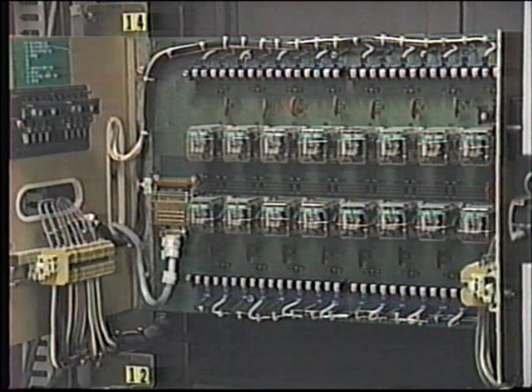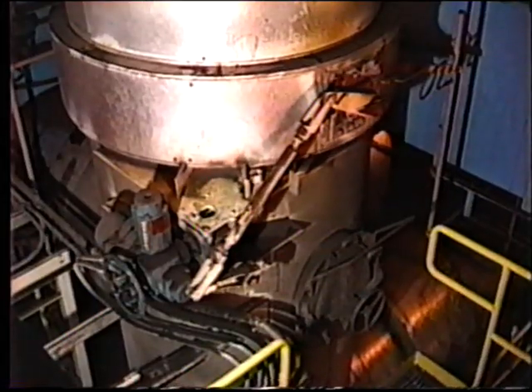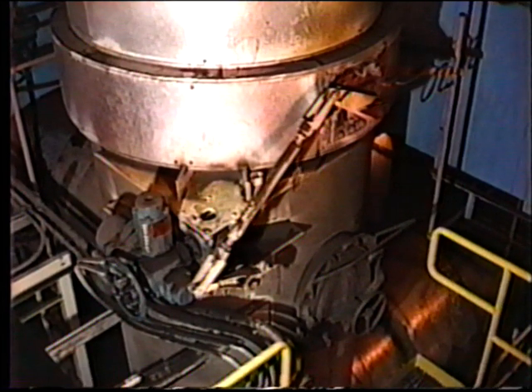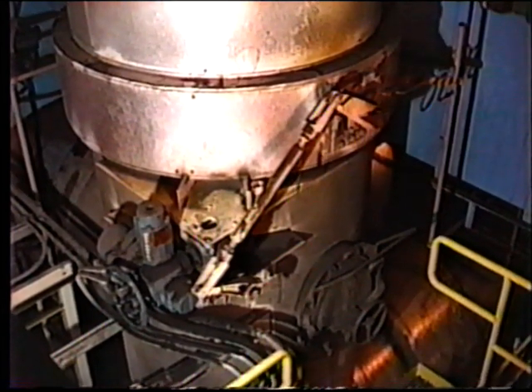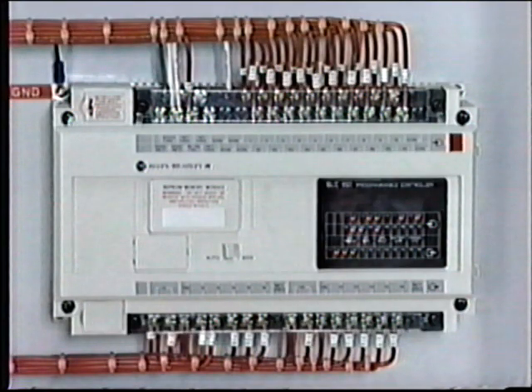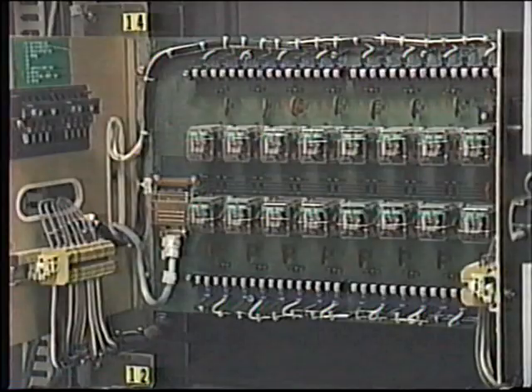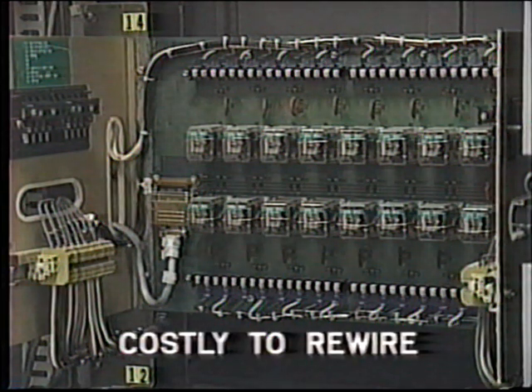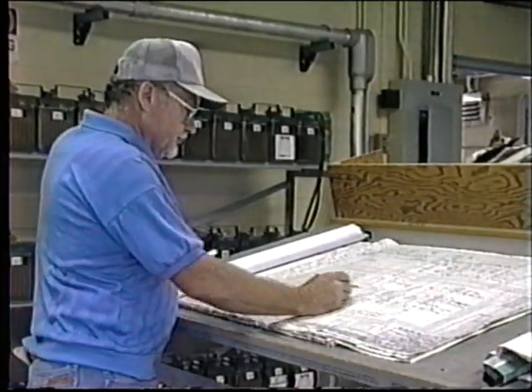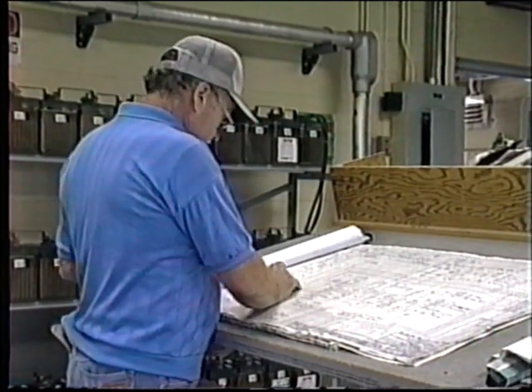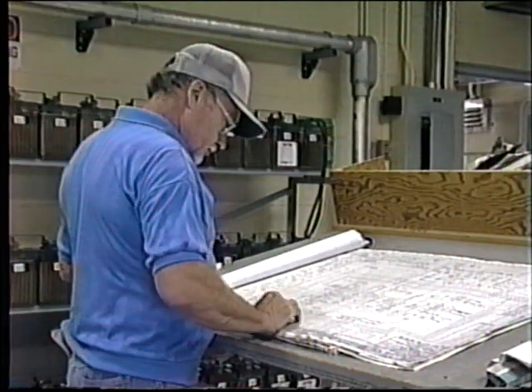Traditionally, control has been performed by hardwired relays which open or close contacts to operate control devices in a specific sequence, depending upon the input signals. In the much smaller PLC, control is performed by the computer software opening and closing switches in response to input signals. Moreover, once a hardwired relay panel is installed and wired to perform a specific function, a great amount of effort would be required if the control process requirements were to change. We would need to sit down and redraw the circuits, perhaps purchase additional equipment, and then rewire the components.